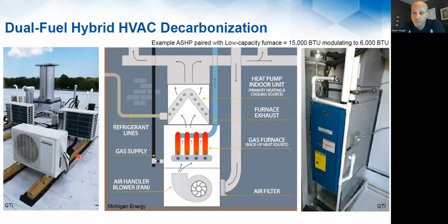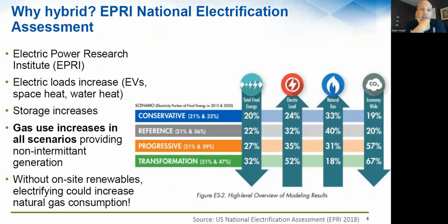You'll set it up as a dual fuel. You'll tell it you have a heat pump and a gas furnace combo. You'll tell it the temperature you want to switch between the two. And that's it. Based on outdoor temperature, it switches between the two. You've got to do the math to figure out what that temperature is, but that's how it would in fact work.